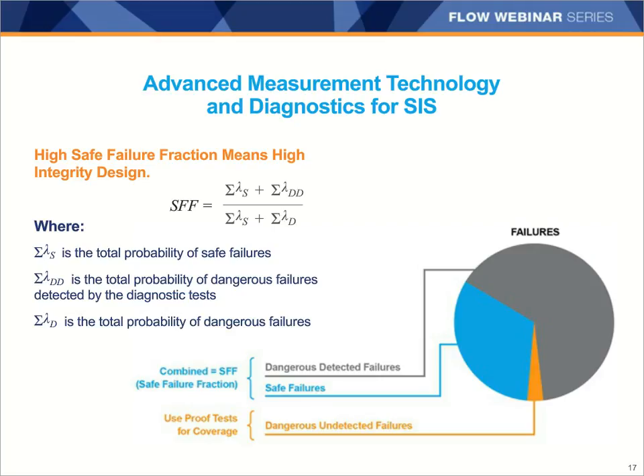The dangerous failures, or failures that have the potential to put the safety instrumented system into a hazardous or fail to function state, are split into two different categories. Those are the detected ones and the undetected failures. Detected dangerous failures are ones that have diagnostic coverage so that you would be notified of the failure and be able to take the appropriate corrective action to allow for a safe shutdown of the process. So the safe failure fraction is the amount of failures that are either safe or dangerous and detected. A high integrity design for instrumentation will have a high SFF. Proof testing is then used to try to look for those dangerous undetected failures.